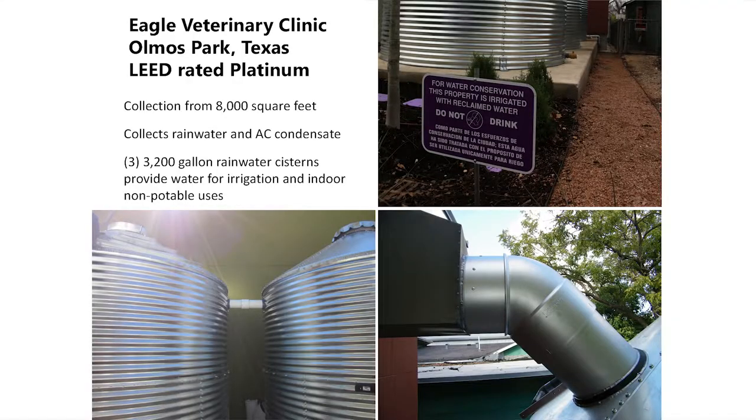Here's a project in Olmos Park, a small town just north of San Antonio — a veterinary clinic that wanted to be LEED certified and do something really neat. Collecting from 8,000 square feet of both rainwater and AC condensate into three 3,000-gallon systems. SAWS was really involved, wanting feedback on water savings, so they provided water meters to meter the AC condensate, the rainwater going out, and the makeup water coming in, all hooked to their SCADA system.